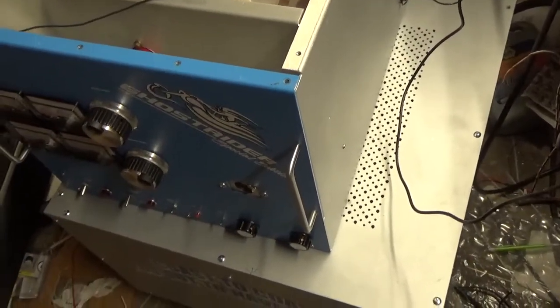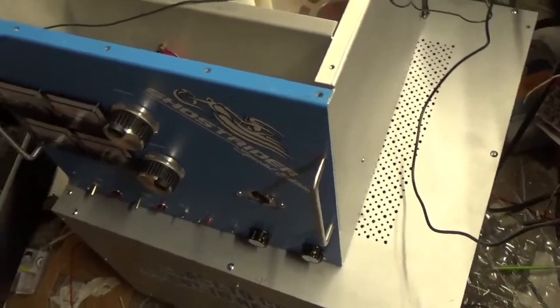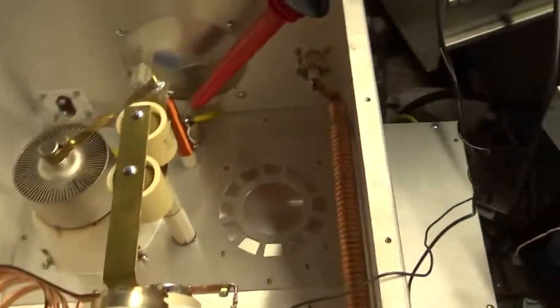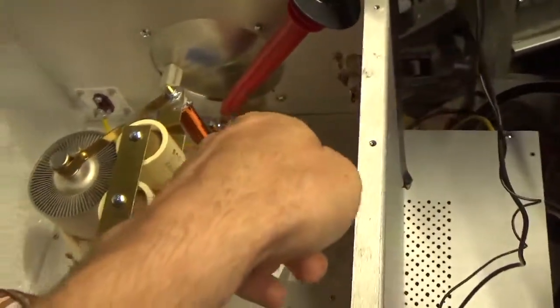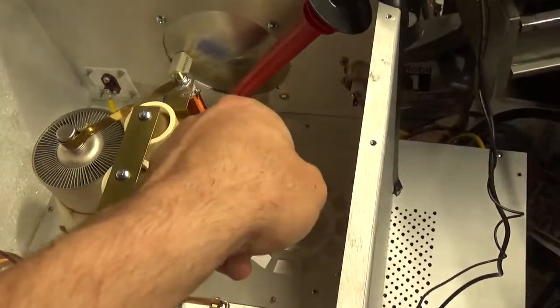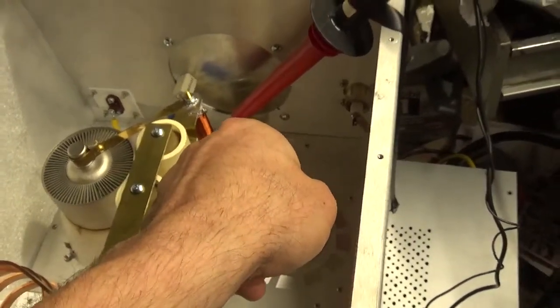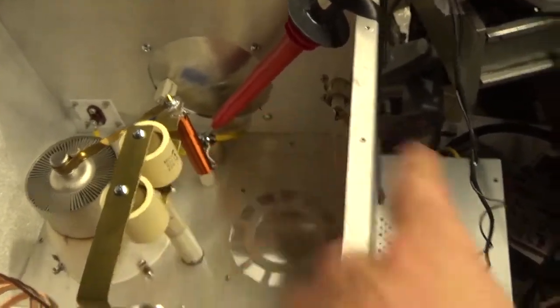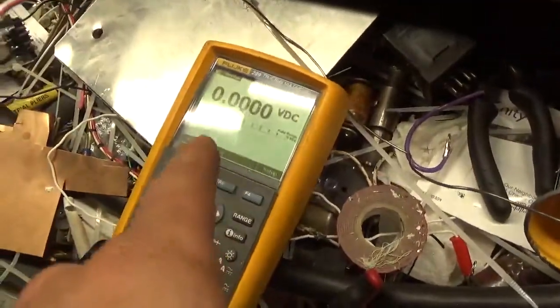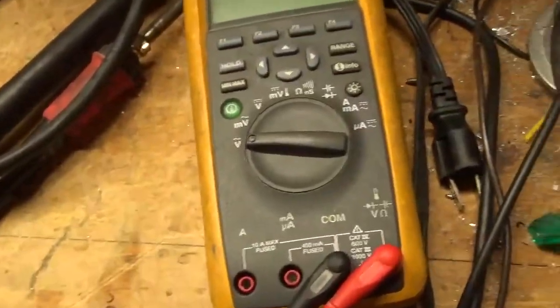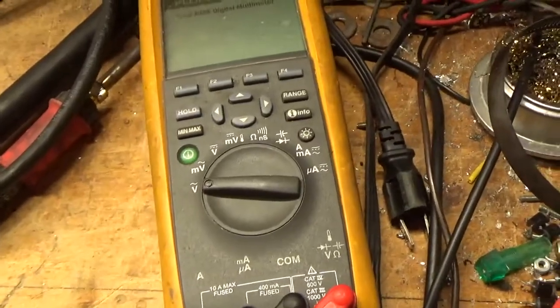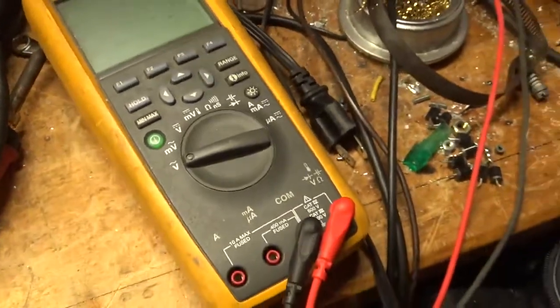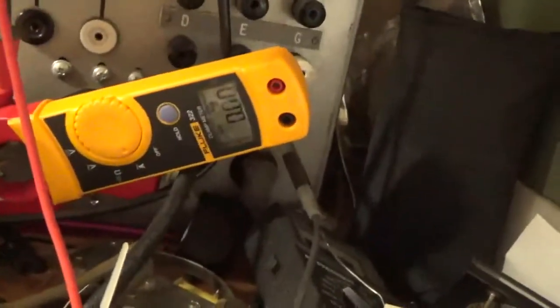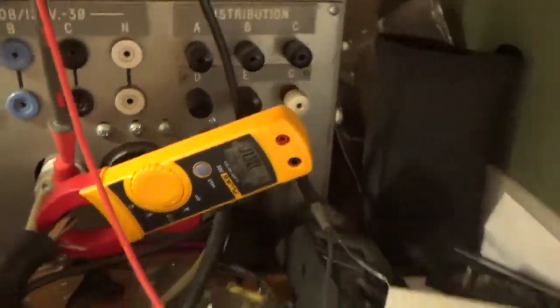Okay, so we're going to simulate the same test as before. Just to recap, we have the Fluke high voltage probe connected to the RF cold end of the plate choke, where it's fed the B positive from the plate supply. We have the Fluke 289 meter connected to the probe. We have the Fluke 287 connected to the line. And then we have the Fluke 322 current meter. Sorry for the mess.